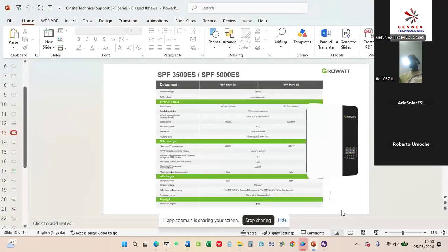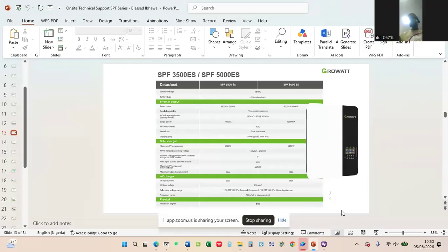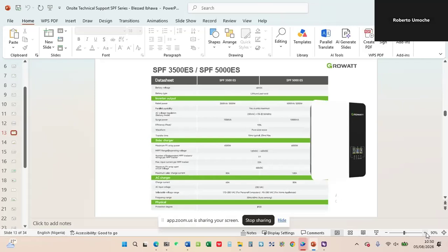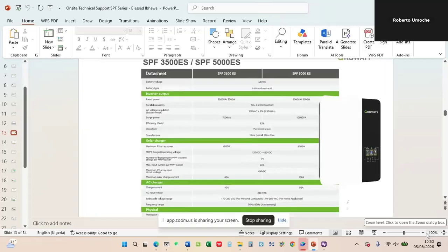If you look at this machine, we have the max solar PV power at 6,000. For the PV side, for us as the service center, most issues come from PV, grid, and then also the battery. But most of the time it comes from the PV, especially for customers used to low frequency inverters, where it looks strange for them to connect maybe 7 panels in series.